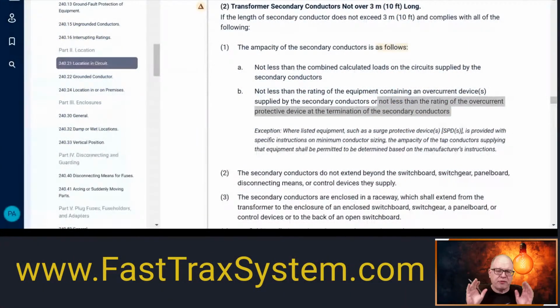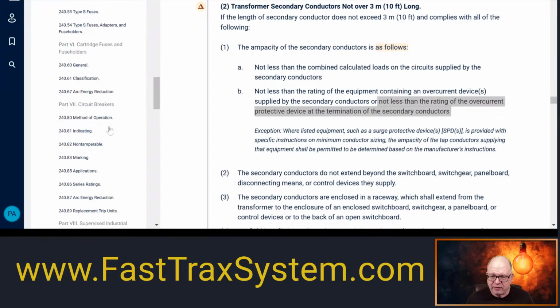But those secondary conductors, if they terminate into a 200 amp device, then they have to be rated for 200 amps. Now, the next biggest thing is the question of, let's say, for argument's sake, it is being terminated into a 400 amp overcurrent protective device in a panel. The transformer's sized properly, loads have been calculated, and those secondary conductors are going to terminate into a 400 amp overcurrent device. Since it's terminating into a 400 amp device, those conductors have to be rated for 400 amps. Well, some engineers, not all, will design it and say, well, the transformer is load limiting, and so on. I want you to use a 500 kcmil. Well, a 500 kcmil has an ampacity of what?